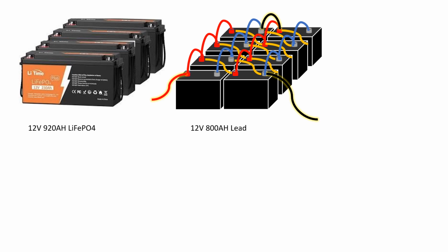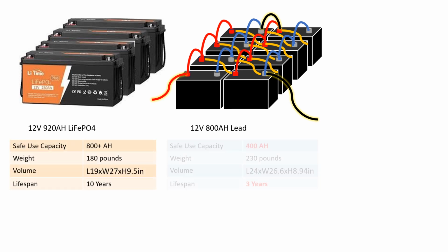So for us here on Sarpedon, we wanted to put in 4 of the lithium iron phosphate batteries, giving us a battery bank rated around 920 amp hours. We're going to hook these up in parallel so the voltage stays the same, but we increase the amperage with each battery. To do the same thing with golf cart batteries, we would have needed 8 of those 6-volt batteries. Let's do a comparison on how those numbers would have worked out.